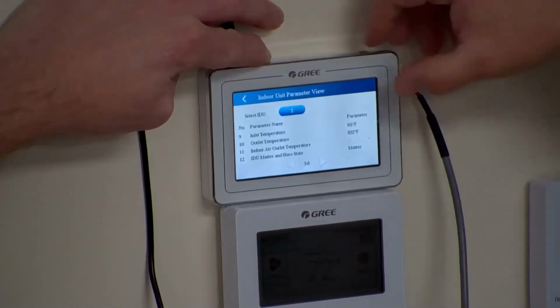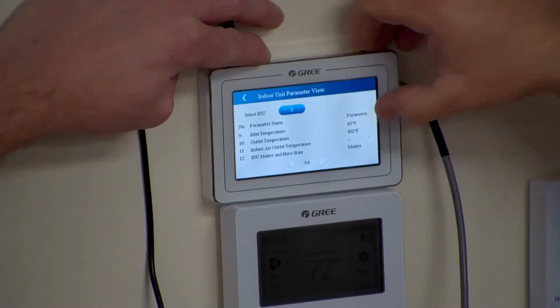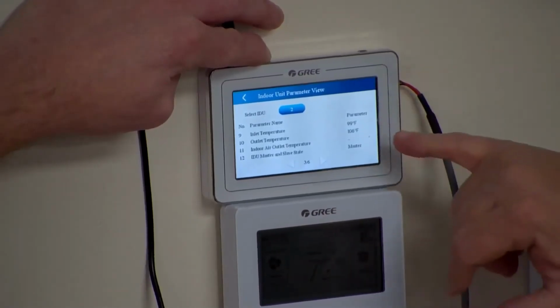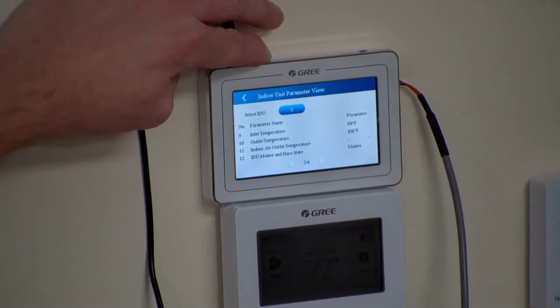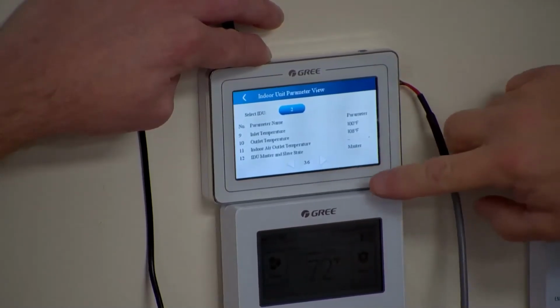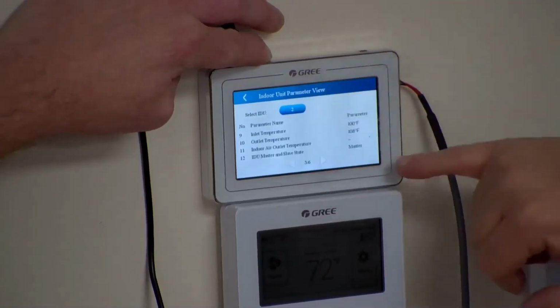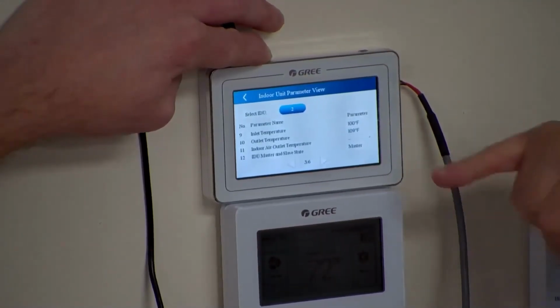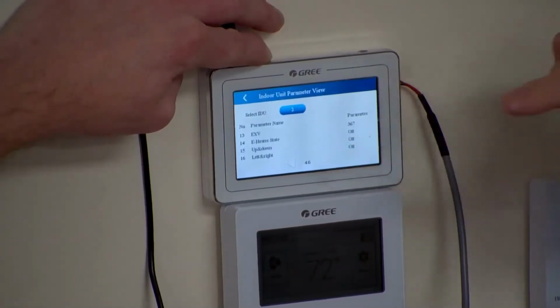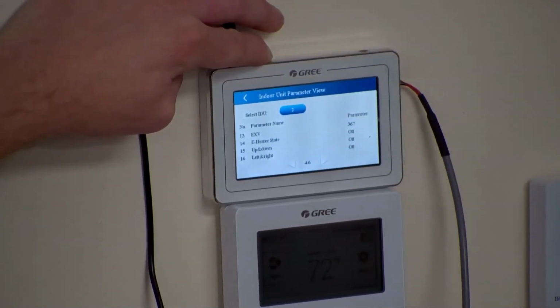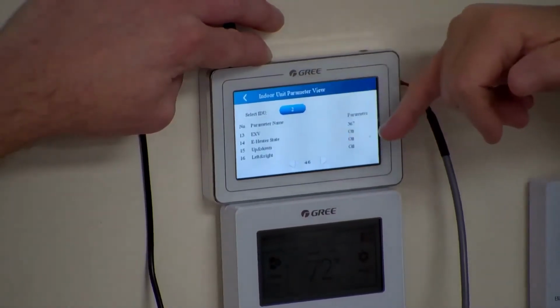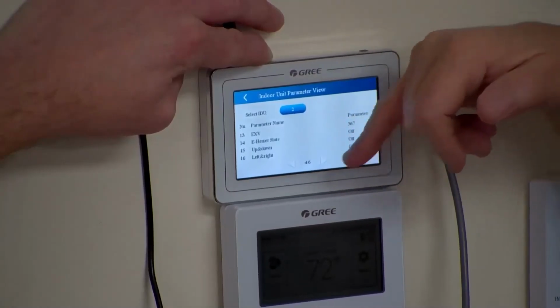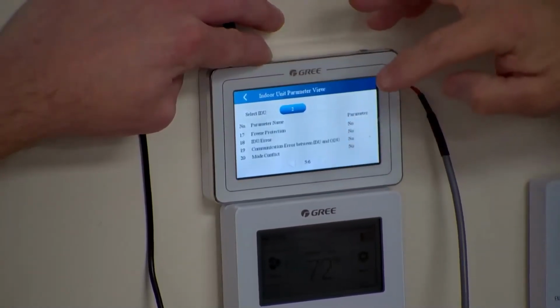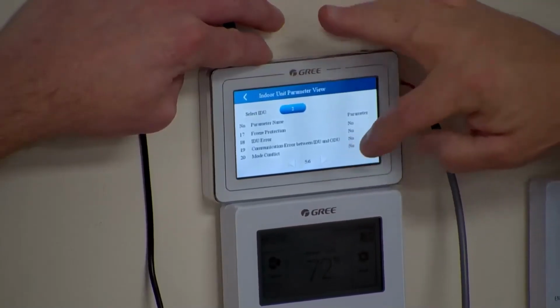Inlet temperature's 91. We're running in heat mode. So now that's actually the outlet. Our inlet is 104. So if we give it a little bit of time, that differential is going to go up. That's what I want to see. This unit number 2 is also the master indoor unit. That also tells us that. The EEV steps, 367. E-heater's off because this one doesn't have an E-heater anyway. Left, right, that's our louvers, freeze protection, all of that.